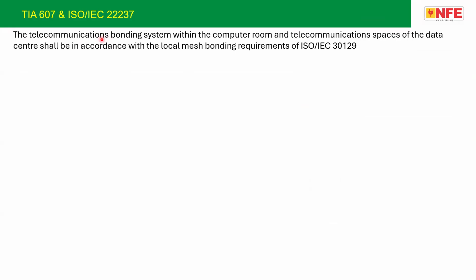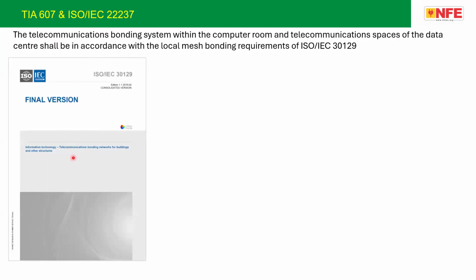Similarly, telecommunication bonding system. A lot of customers ask to make the demand of compliance with TIA 607. I just try to make a comparison of what is there in 22237. For example, 22237 says telecommunication bonding system within the computer room and telecommunication space of the data center shall be in accordance with the local mesh bonding requirement of ISO 30129. I will just try to explain what exactly this is. Basically, the subject is explained in ISO IEC 30129.